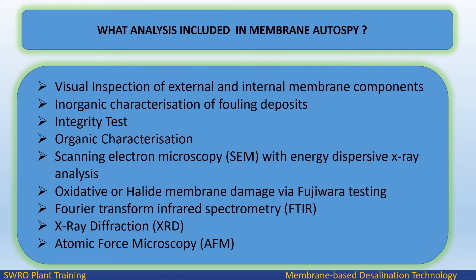What analyses are included in a membrane autopsy? These include: visual inspection of external and internal membrane components; inorganic characterization of fouling deposits; integrity test; organic characterization; scanning electron microscopy (SEM) with energy dispersive X-ray analysis; oxidative or halide membrane damage via Fujiwara testing; Fourier transform infrared spectrometry (FTIR); X-ray diffraction (XRD); and atomic force microscopy (AFM).